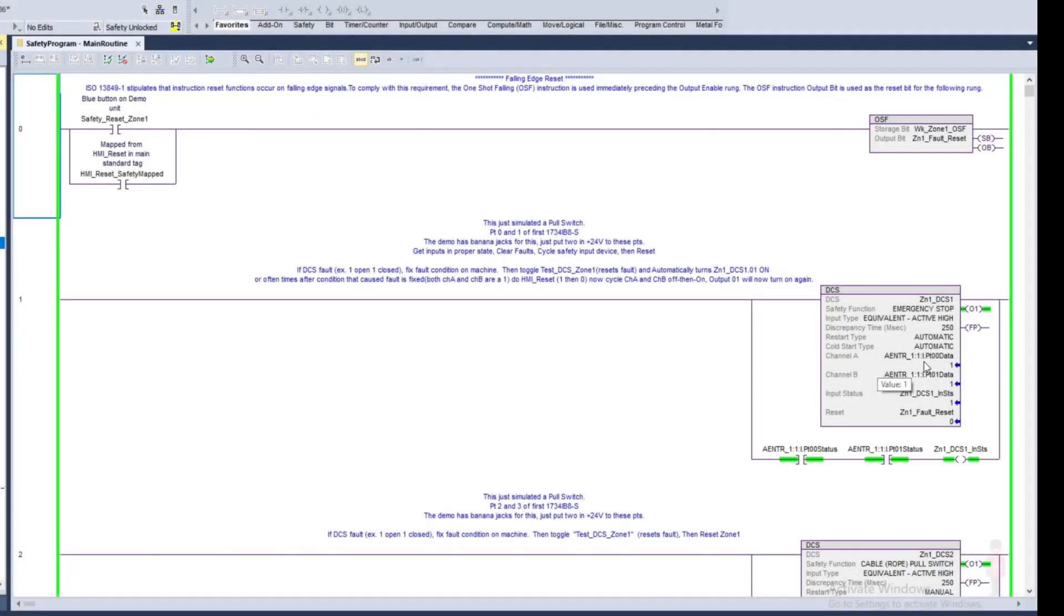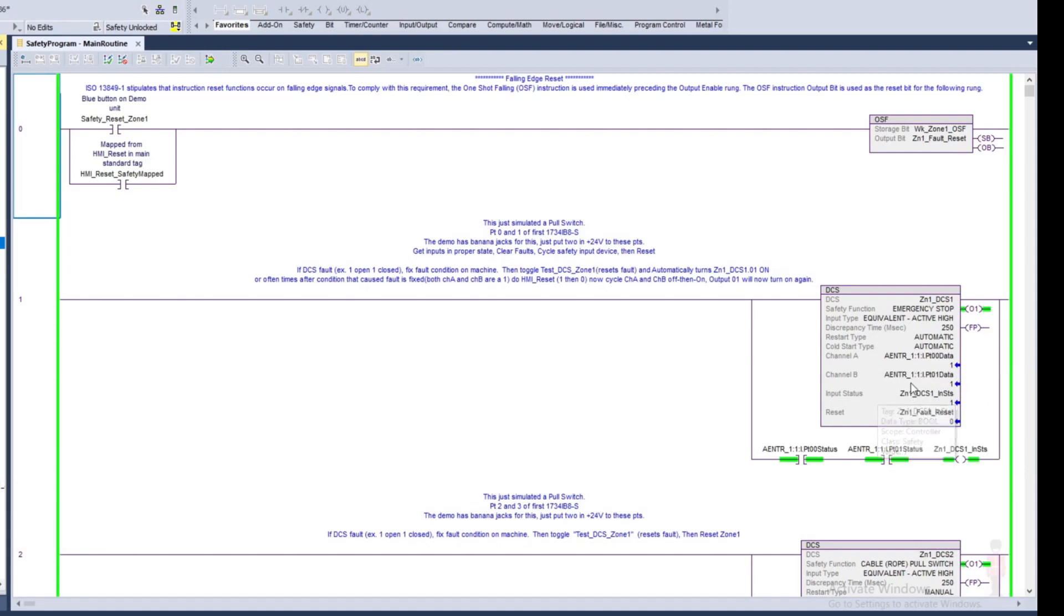I will basically show how I'm using a dual channel stop. I set it up, I give each DCS a name, just called it Zone 1 DCS 1. I am using two channels because I'm simulating an emergency stop. The e-stops have two contacts, one going to point zero, the other one going to point one.